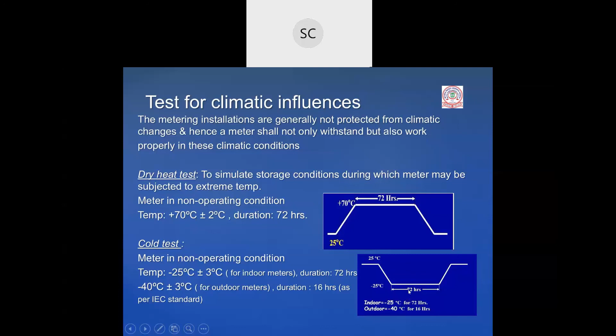Temperature is varied, and humidity is also varied. At 25 degrees, humidity is 96%, and at 45 degrees, it is 93%. The slope is also defined in the standard, and it is a 6 day cycle, with each cycle of 24 hours. That means for a total of 6 days we have to maintain the same conditions, and the meter should work properly. That is very important, sir.